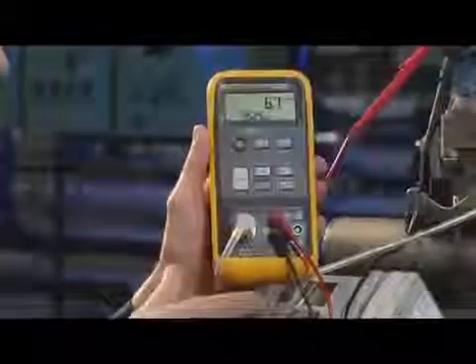In the first step we want to measure 0 inches of water. The best way to do this is to vent to atmosphere. We do that with these controls. Open the vent valve. The vent valve can be opened or closed, open for measuring the 0 inches of water point.